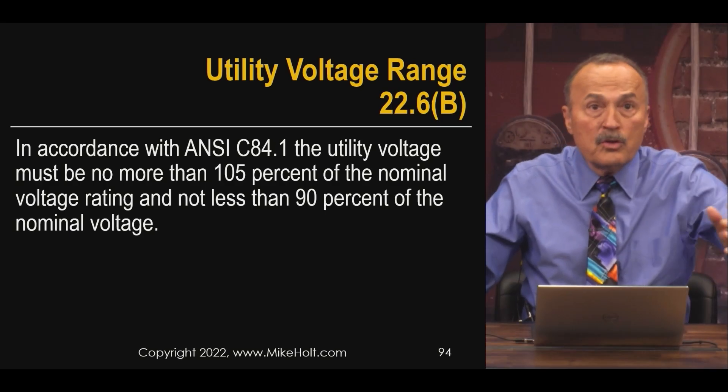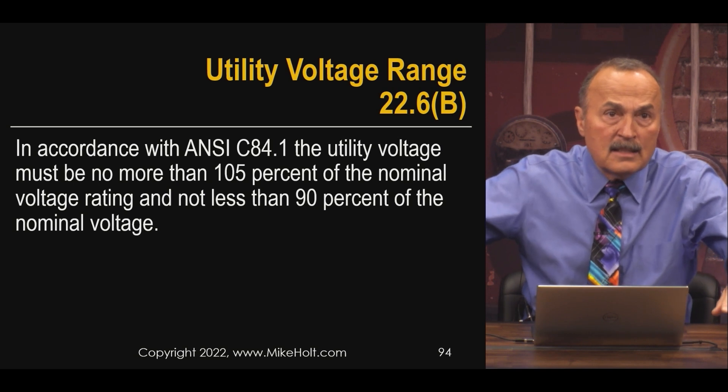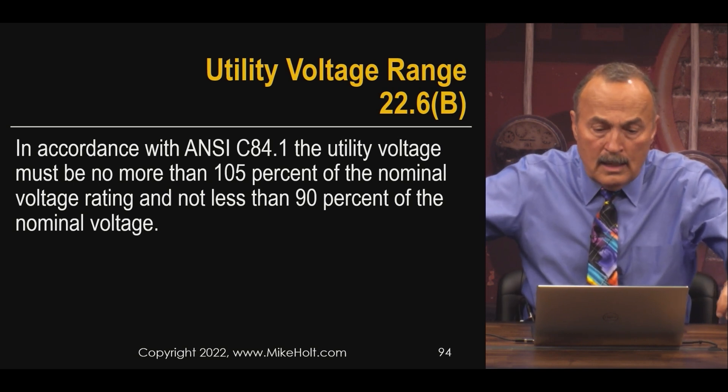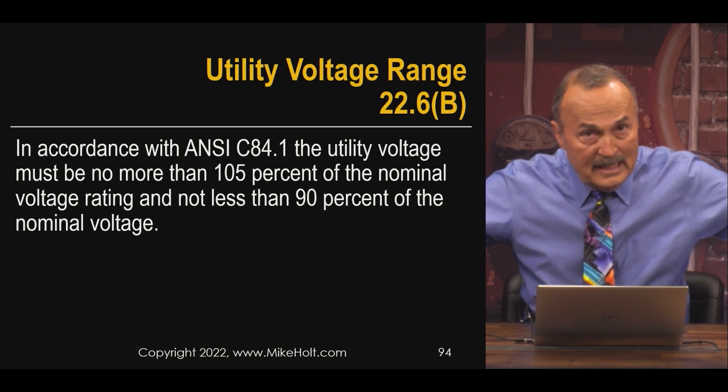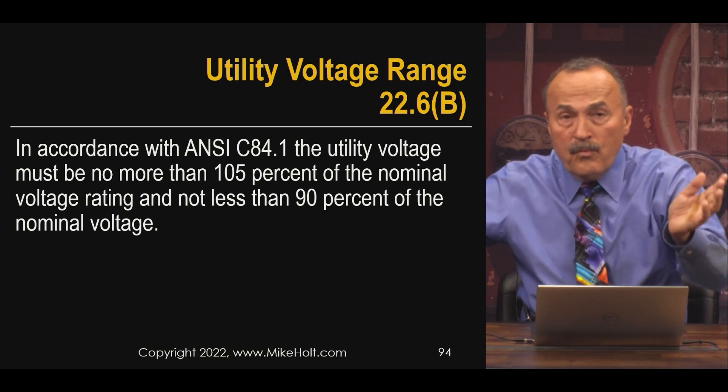So when you hear somebody talking about 110, and houses at 110, maybe 115 — I'm sure there are transformers out there giving you 115 — and 120 is because it's the history of voltages. Today, nominal system voltage is 120/240. There's an ANSI standard for utilities: according to ANSI C84.1, column A in the table, the utility voltage must not be more than 105% of the nominal system voltage.